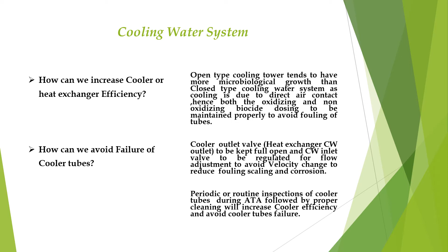Cooler outlet valve, that is heat exchanger cooling water outlet valve, to be kept fully open and cooling water inlet valve to be regulated for flow adjustment, to avoid velocity change in the cooling water flow, to reduce fouling, scaling, and corrosion. Periodic or routine inspection of cooler tubes during annual turnaround, followed by proper cleaning, will increase cooler efficiency and avoid cooler tube failure.